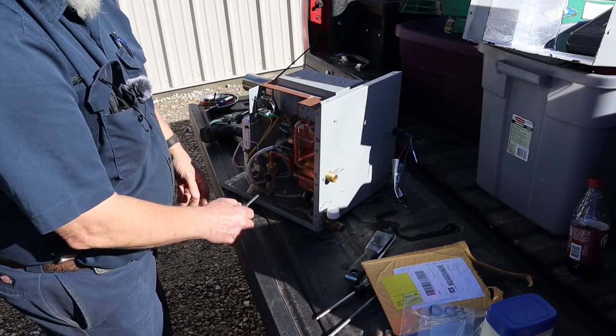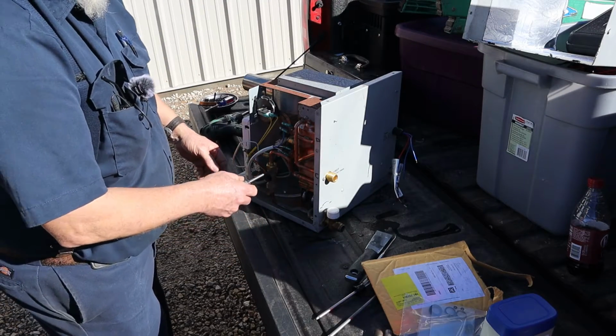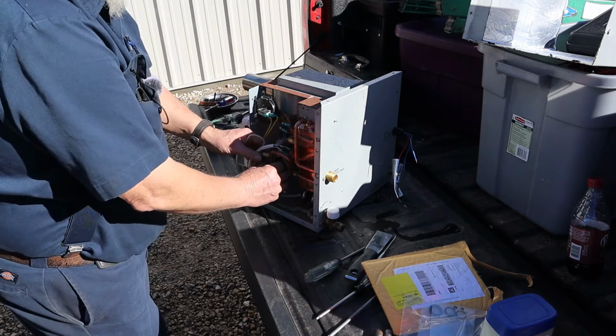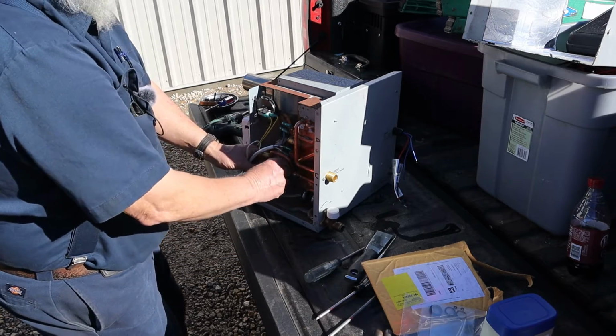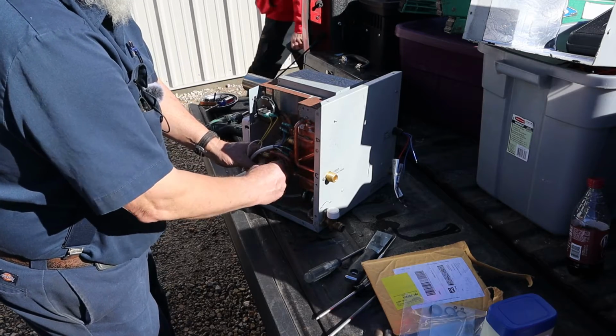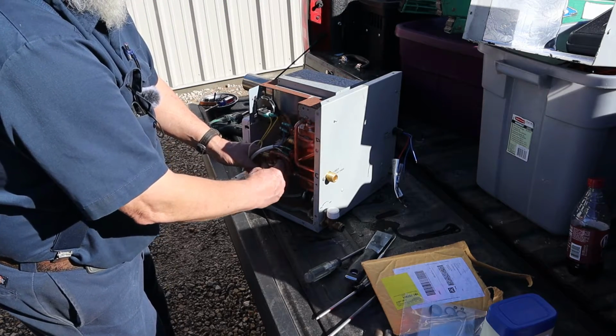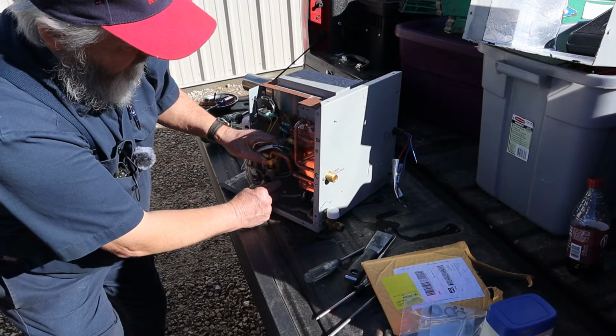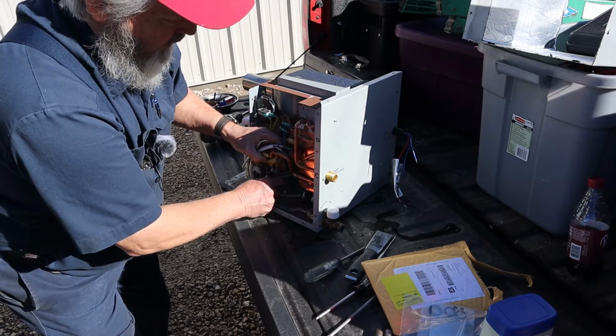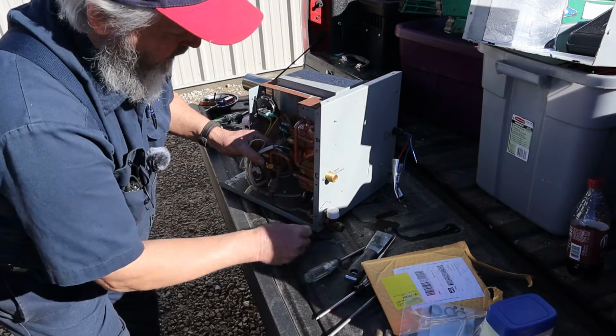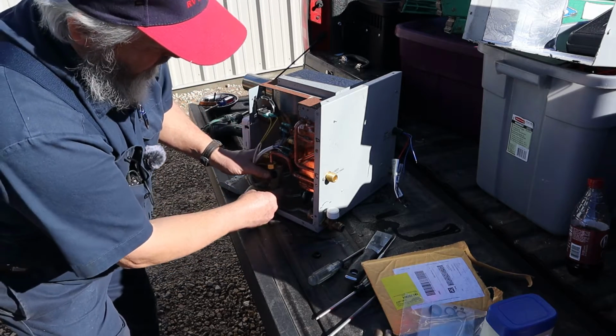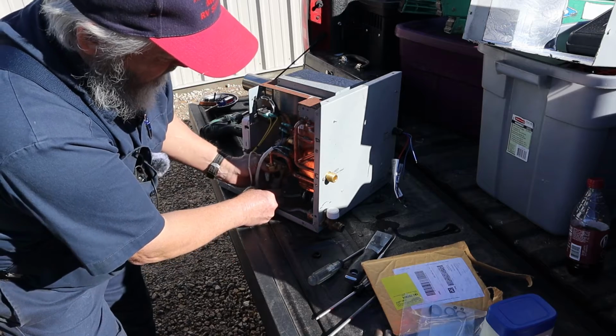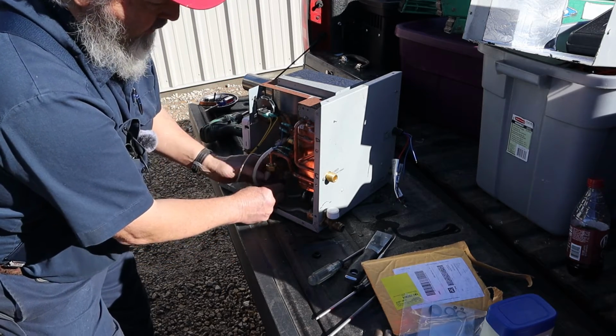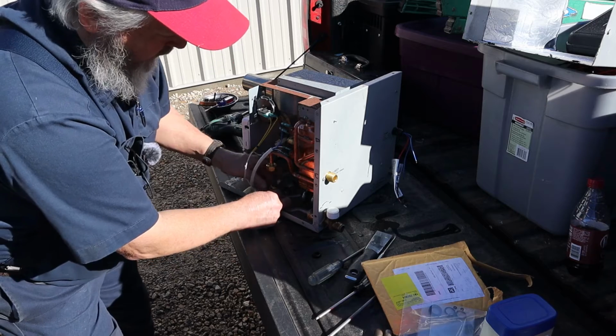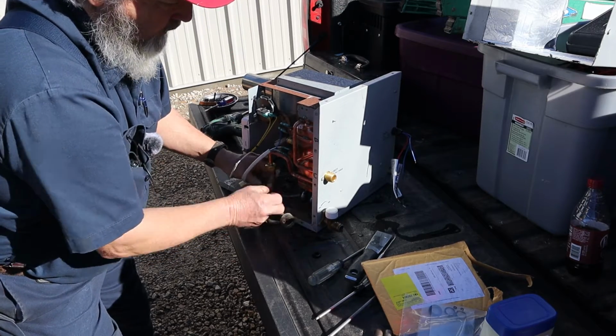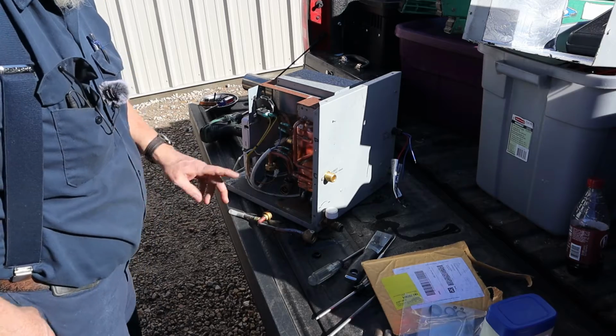Okay, so I got these 2 screws out to hold this pipe. We'll have to take this loose right here. This pipe here is where your flow sensor's at. Let's get that flow sensor off there, and then we can get this pipe off right here, and that exposes all our O-rings.